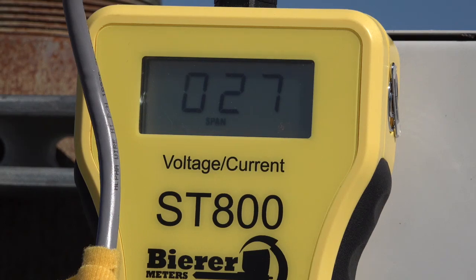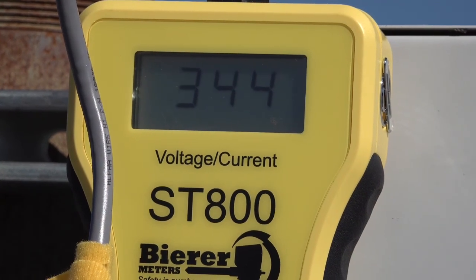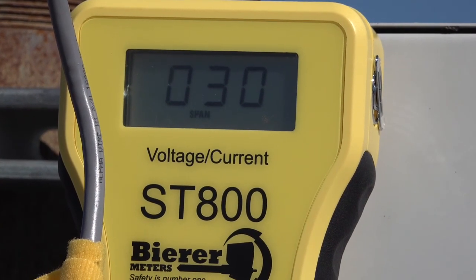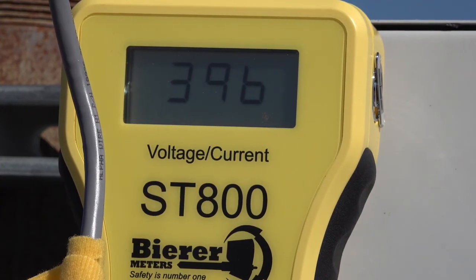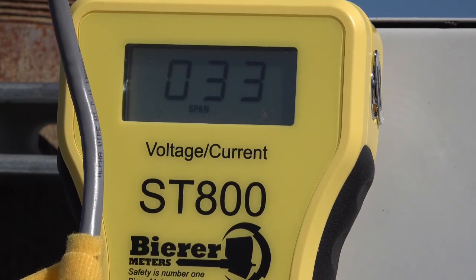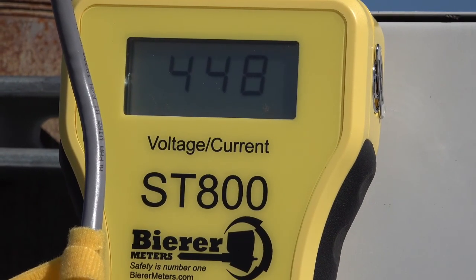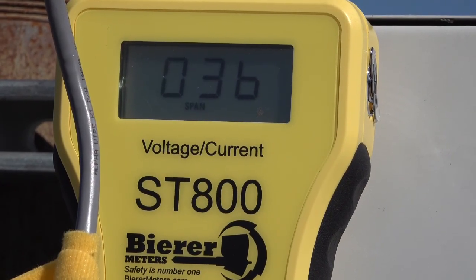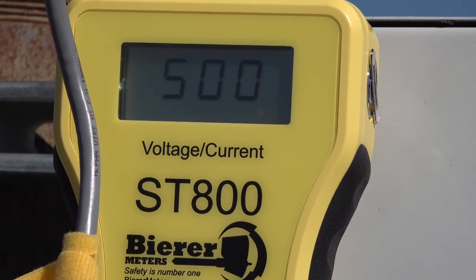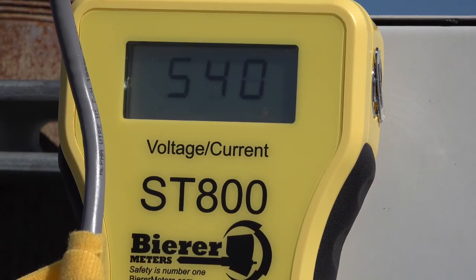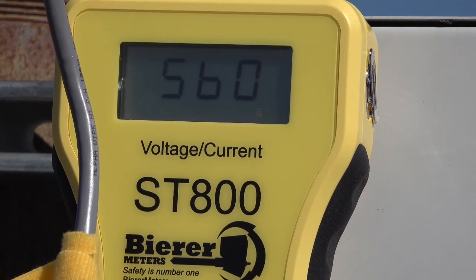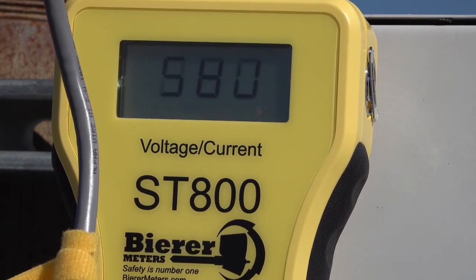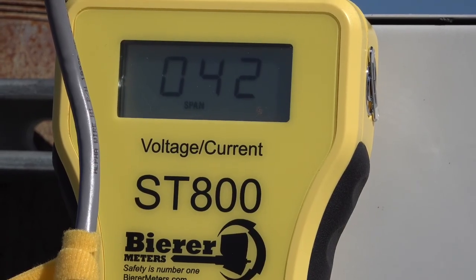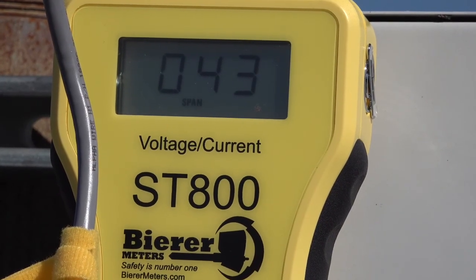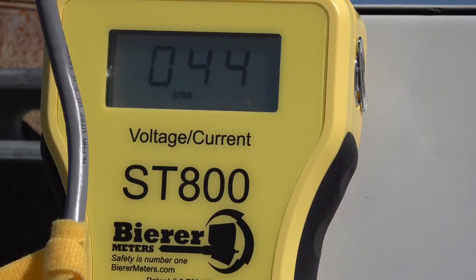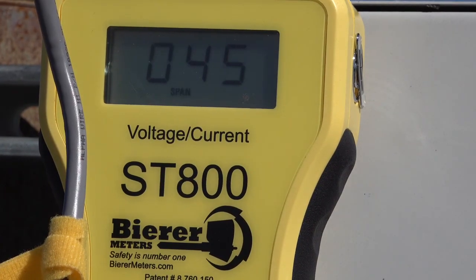As I zoom the camera in here, let's focus our attention on something very important. As the ST800 gradually increases in count, we want to focus our attention on how much current it increases per count. This information is very important for a couple different reasons. One, if the ST800 current increases approximately 8 amps or greater per count, then we know the conductors that the leads are attached to are able to source a high amount of current, and more than likely the ST800 will achieve 800 amps fairly easily.